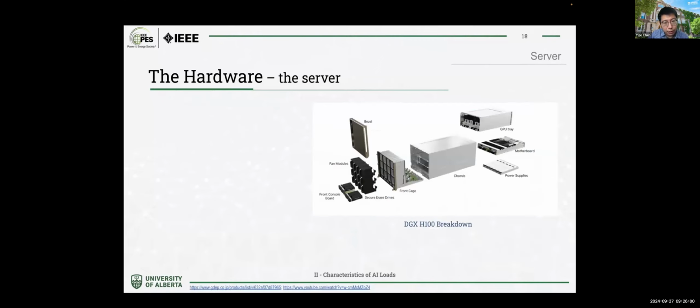For current advanced GPUs, for instance the H100, which is integrated into the NVIDIA DGX system, one DGX system has a maximum claimed power consumption of about 10.2 kilowatts, including 8 H100 GPUs. Most of the time, if you are training an AI load, based on the news and observations, it often reaches 9 to 10 kilowatts under full load.